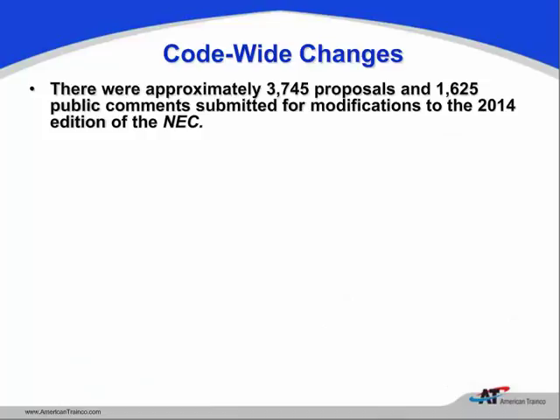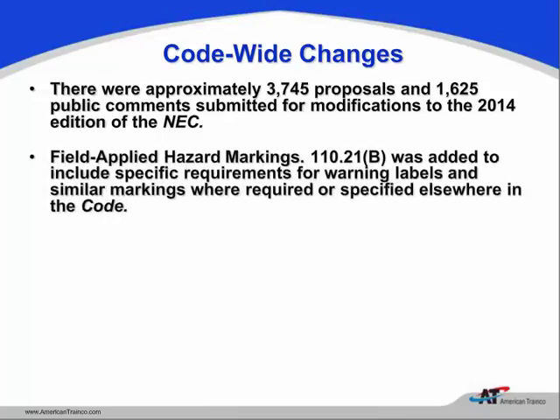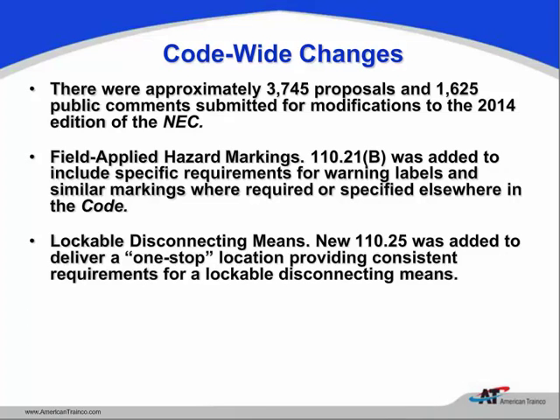Let's look at code-wide changes—what the committee calls global changes. There were 3,745 proposals and a lot of public comments, and it took the technical committees time to work through these changes. One global change that appears throughout the whole code is 110.21B, which is going to be patterned after the ANSI Z535 standard. Another global change involved 46 proposals to relocate all requirements for lockout tagout into one section—110.25.